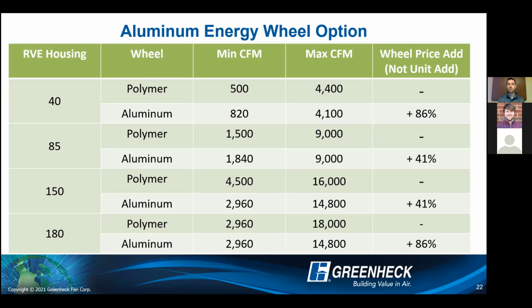Reason being is, and we'll touch on frost control, but aluminum wheels, we require that VFD to be standard on the aluminum wheel for frost control. So it's a modulating wheel frost condition just because there's more risk with aluminum wheels getting damaged during frost conditions compared to polymer wheels. Also, they get a little heavier, so there's risk on belts and motors becoming less useful over the lifetime. So that is why we have that. So if you were to add a VFD on the polymer wheel as well, these differences in price would also shrink because then they would be more apples to apples. But another thing to point out is the maximum CFM between the two also changes. So you can see in each housing, except the 85 housing, the polymer wheel moves a little bit more airflow from an overall housing standpoint. So we do go up to 14,800 on the aluminum, up to 18,000 on the polymer type energy recovery wheels.